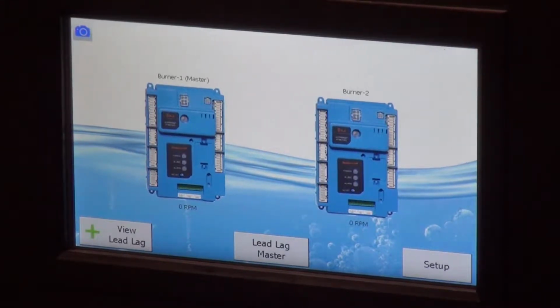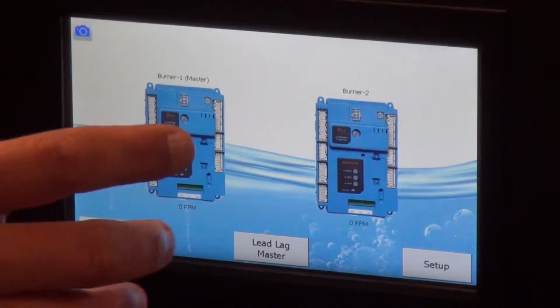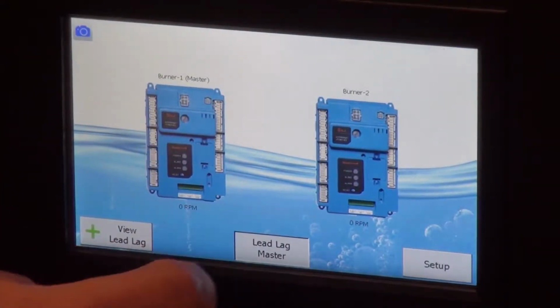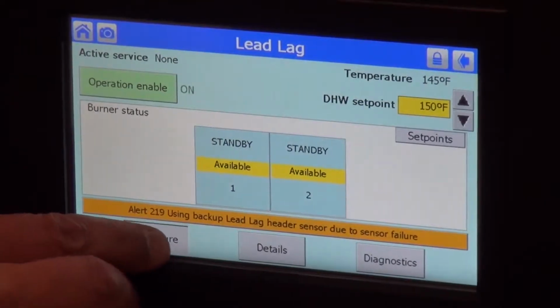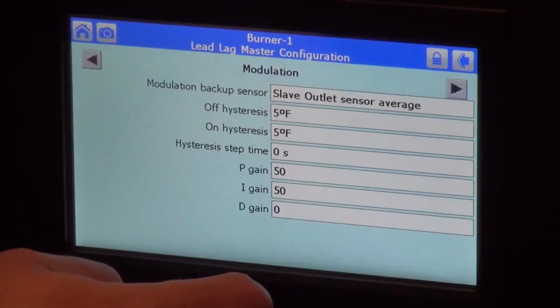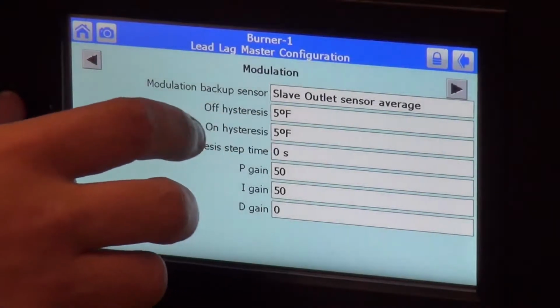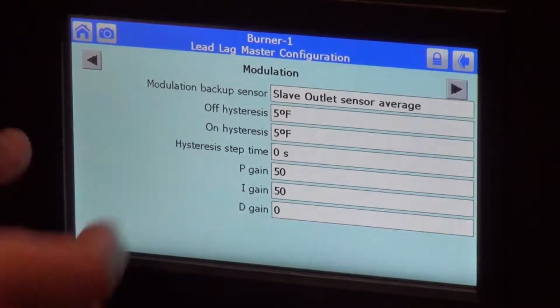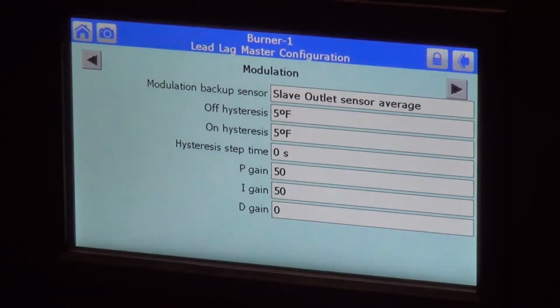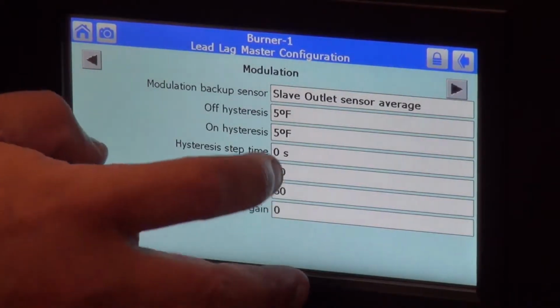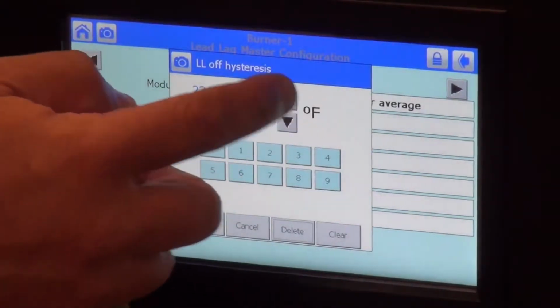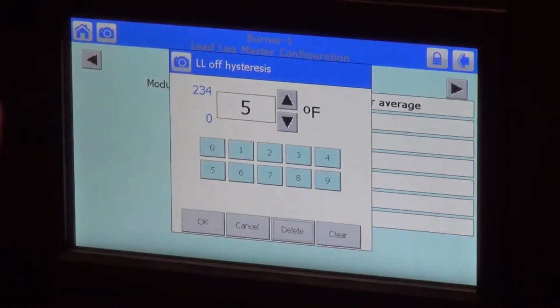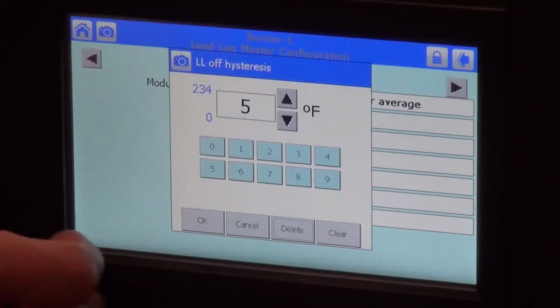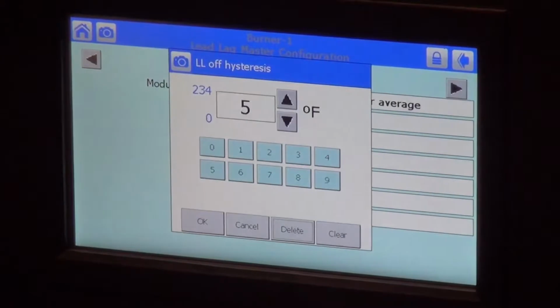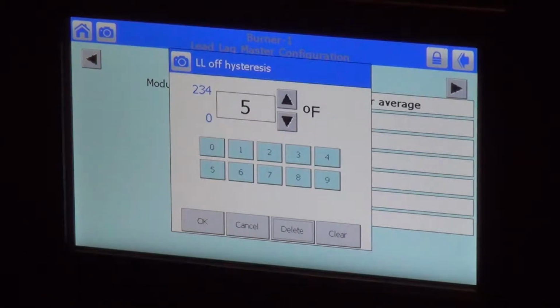And the set point differential is actually controlled by this guy, but I'll also show you how you can do it on this as well. So if we go to our lead lag master on here, we go to configure, we go over to advanced settings, you'll see it says hysteresis on it. It's got a 5-degree on here on off and on. Hysteresis is Honeywell's way of saying temperature differential. So we could click on that guy and we could up that or down that to actually create whatever delta T we wanted through these boilers on there. So if I were to put this to 10 to 15 degrees, these aren't going to operate until that thing actually drops down below a 15 degree off that set.